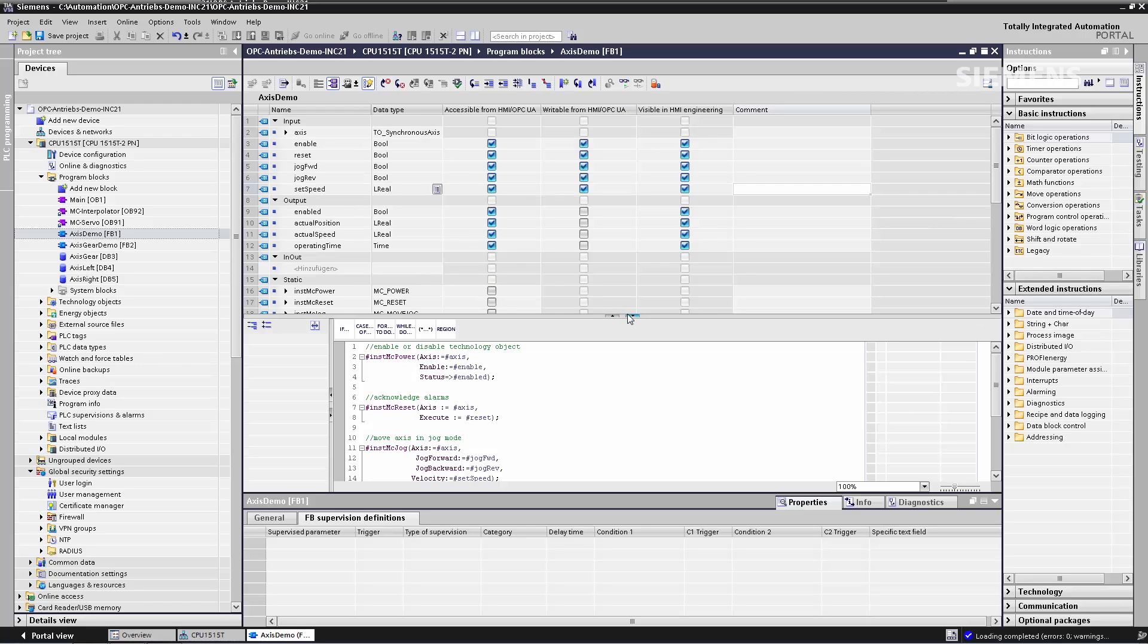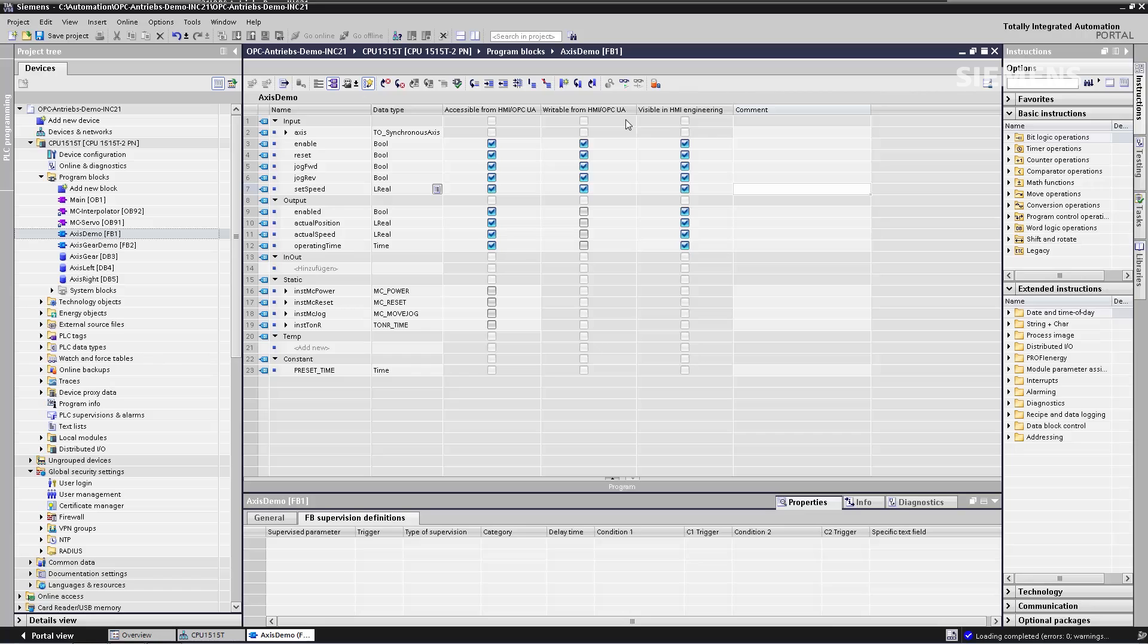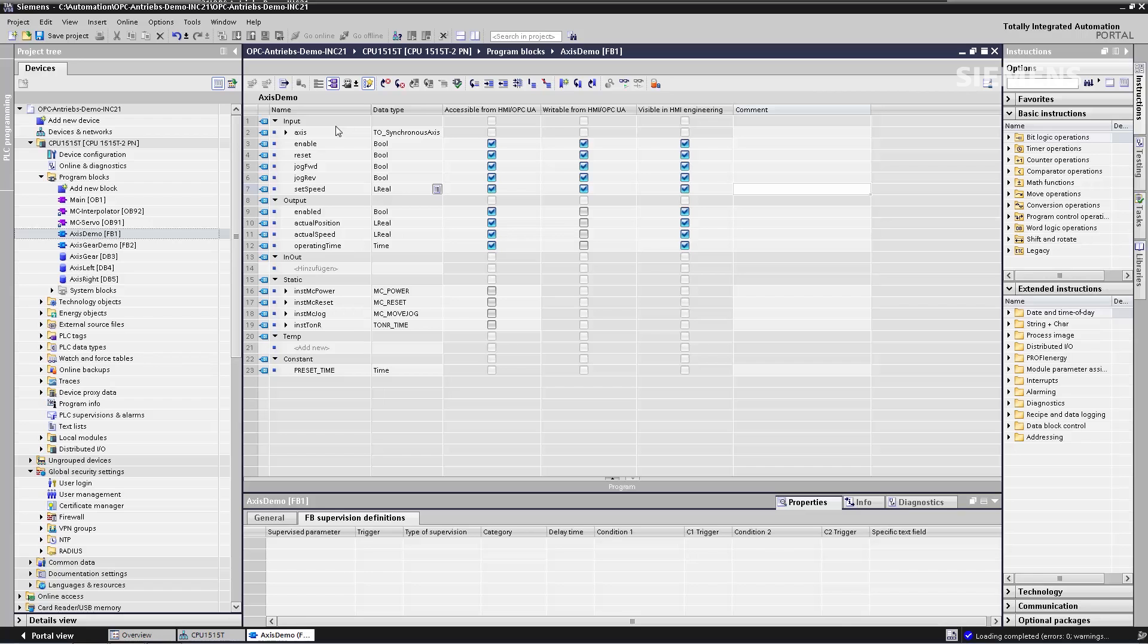Here I'm mainly interested in the columns accessible from HMI OPC UA and writable from HMI OPC UA. They will allow me to precisely specify whether a variable is not accessible at all via OPC UA, if it's read-only or if it's writable for OPC UA clients. In this example, we can see that static variables are not accessible at all via OPC UA, that the output variables are read-only and an OPC UA client has read and write access to the input variables.